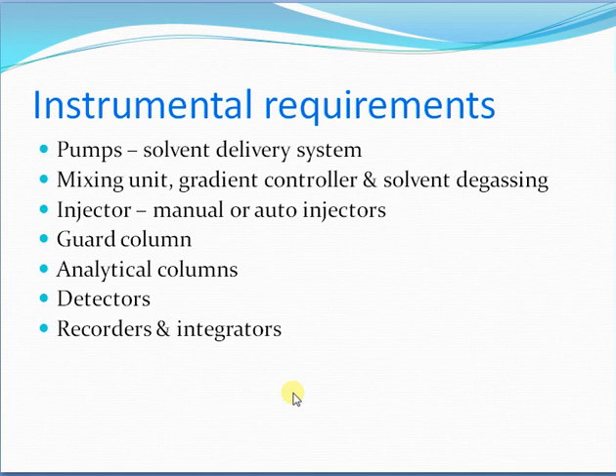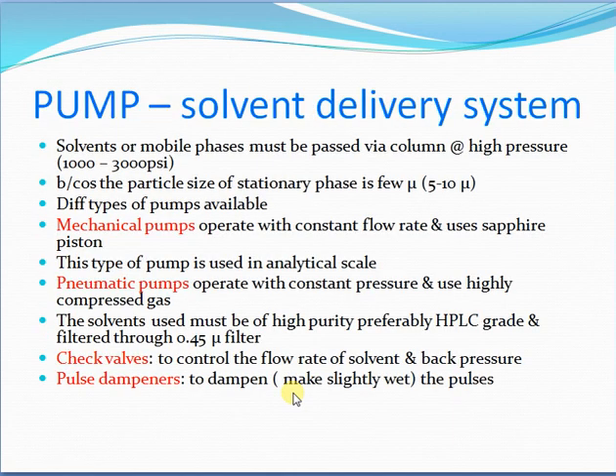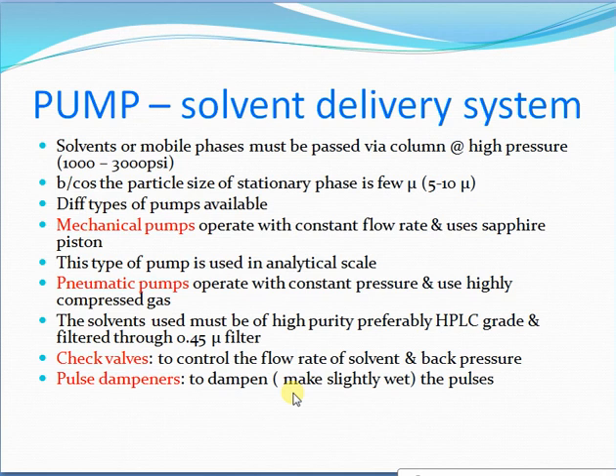The pump is the solvent delivery system, which includes a mixing unit and gradient control. The solvent is degassed before use. The injector can be manual or auto. The pump must push the mobile phase through the column at high pressure — minimum 500 PSI, maximum 5000 PSI, typically 1000 to 3000 PSI — due to the small particle size of the stationary phase, which is around 5 to 10 microns.